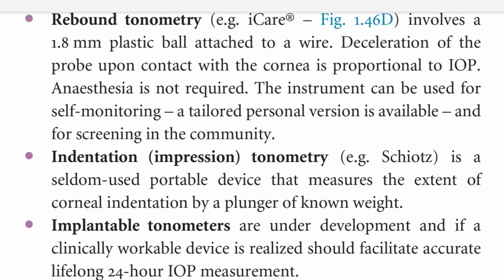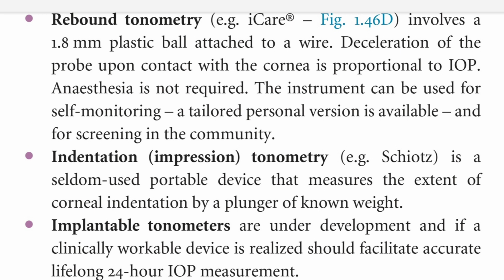Rebound tonometry, for example iCare, figure 1.46d, involves a 1.8 mm plastic ball attached to a wire. Deceleration of the probe upon contact with the cornea is proportional to IOP. Anesthesia is not required. The instrument can be used for self-monitoring, a tailored personal version is available, and for screening in the community. Indentation impression tonometry, for example Schiotz, is a seldom used portable device that measures the extent of corneal indentation by a plunger of known weight. Implantable tonometers are under development and, if a clinically workable device is realized, should facilitate accurate lifelong 24-hour IOP measurement.